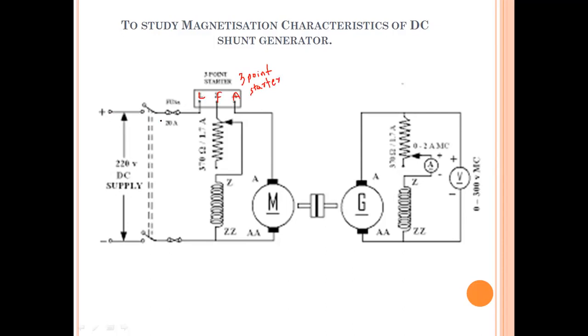Positive of the mains is connected to the line terminal L. The F point, which is the field point of the three-point starter, is connected to a rheostat, and the rheostat is connected to the field winding. The second terminal of the field winding, Z2, is connected to the negative.